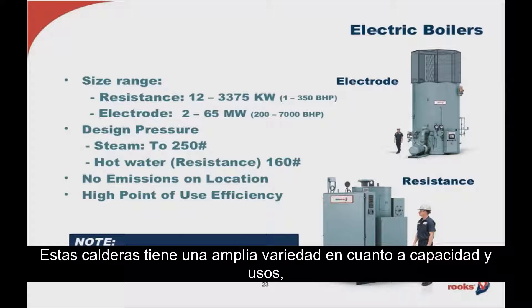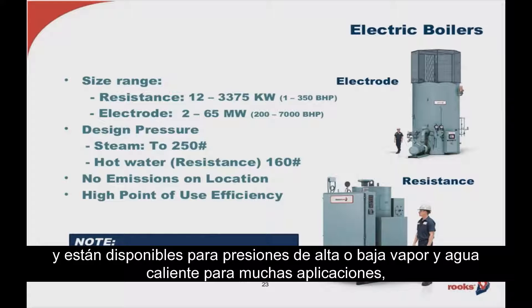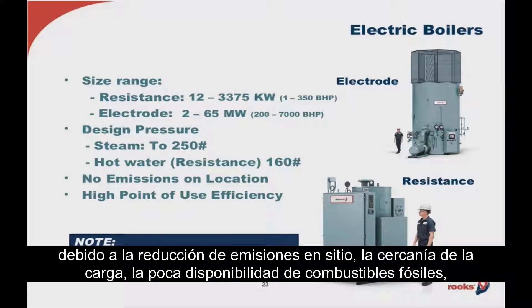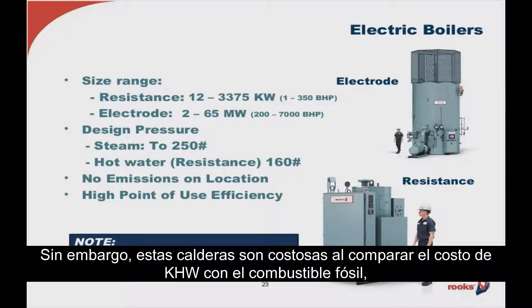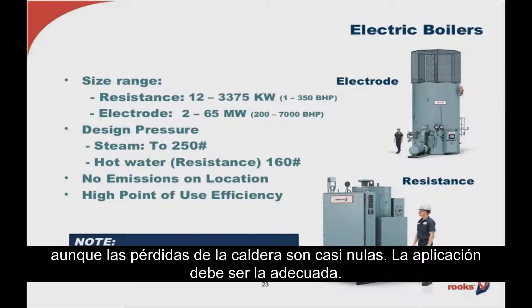These boilers cover quite a range in capacity and uses, and are available for both high and low pressure steam or hot water, in an array of process or heating applications. Main reasons for selection include on-site emission reduction, proximity to load, lack of fossil fuel availability, no stack requirement, and possibly low electric power rates such as hydroelectric generation. Otherwise, these boilers are expensive to operate because of the cost per kWh when compared to fossil fuel, even though losses within the boiler itself are almost nil.